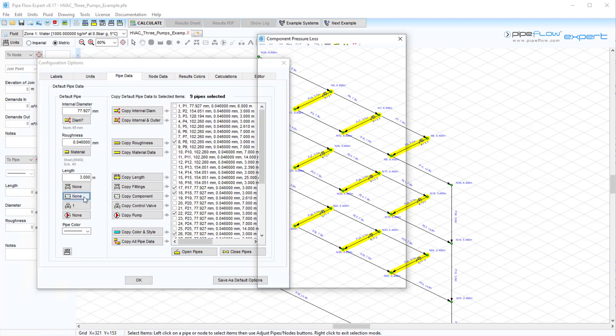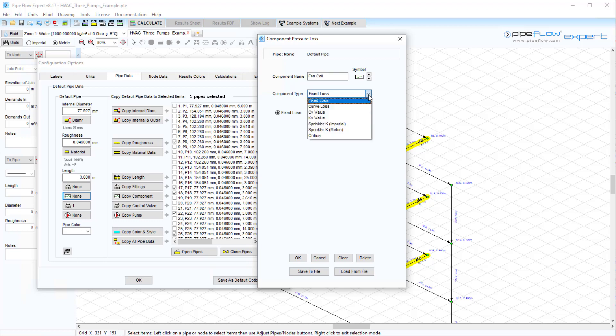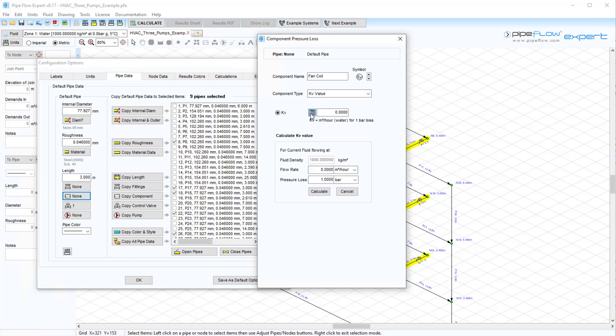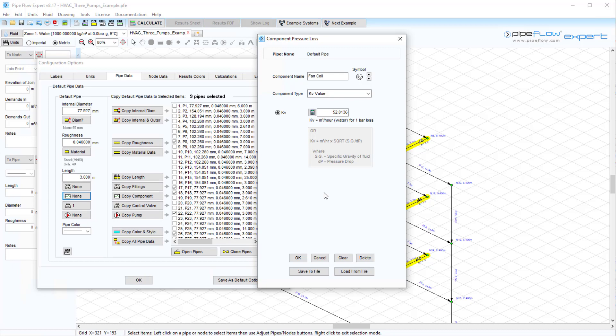So let's say we want to add a fan coil component to all the selected pipes. Let's amend the default pipe data to include a component with a KV value. Here we will use Pipeflow Expert's built-in calculator with a flow of 0.005 m³ per second for a pressure loss of 0.12 bar. The KV value has been calculated as 52.0136. We can also select an appropriate icon for our fan coil.